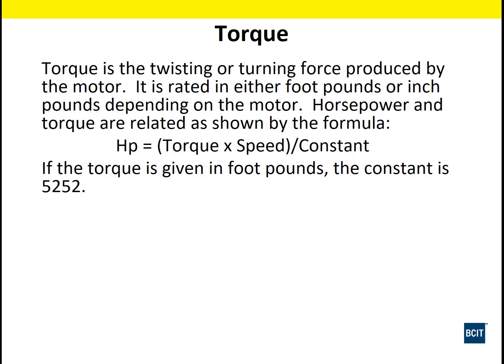We can have a look at that equation here. Torque is the twisting, turning force produced by the motor. We can calculate that: horsepower equals torque times speed, T times N, divided by our constant. Our constant is 5252.